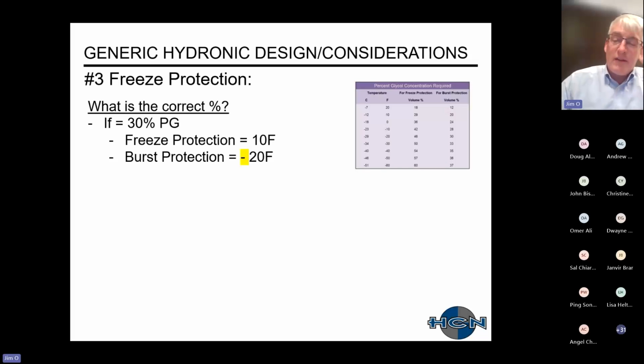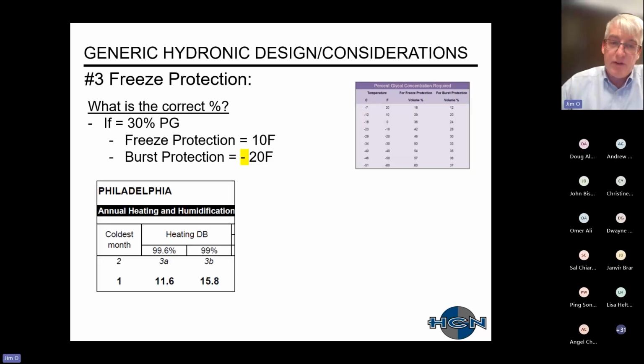So what is a correct percentage of propylene glycol? When I worked in Buffalo, it was automatically 30 percent propylene glycol, tried and true for years. When I worked in Philly, I've seen different variations from 10 to 30 percent. To show the difference, if you have a 30% mixture of propylene glycol, your freeze protection is down to 10 degrees. Your burst protection is down to -20.